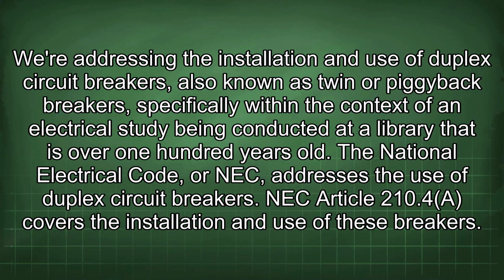We are addressing the installation and use of duplex circuit breakers, also known as twin or piggyback breakers, specifically within the context of an electrical study being conducted at a library that is over 100 years old. The National Electrical Code, or NEC, addresses the use of duplex circuit breakers. NEC Article 210.4 covers the installation and use of these breakers.